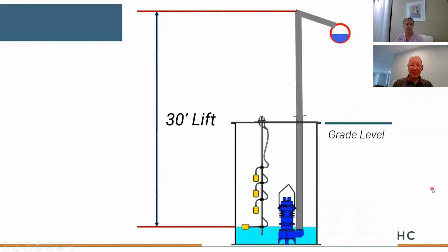So bear with me just a second. What we have to remember with sump and sewage is it's an open system. We tend to have an open pit or an open sump that's full of water, and the only job of this pump is to get water out of the basin, whatever our vertical lift is, to ultimately tie into a city connection.